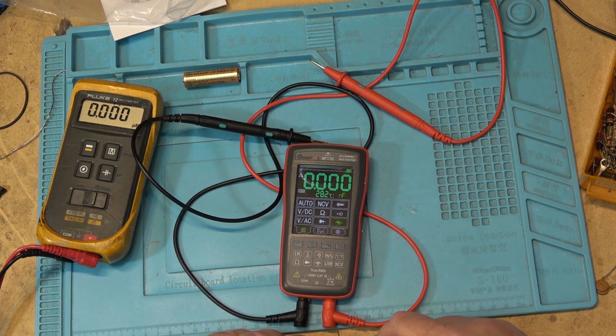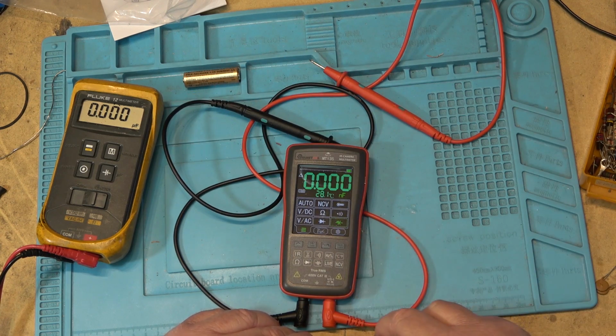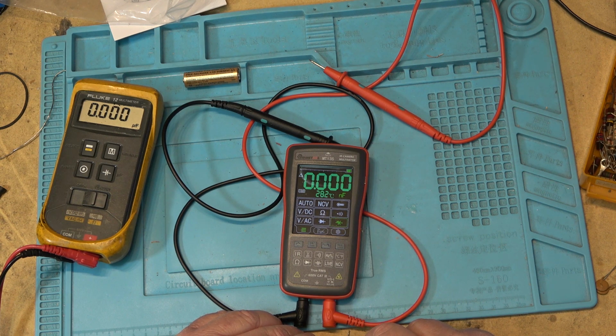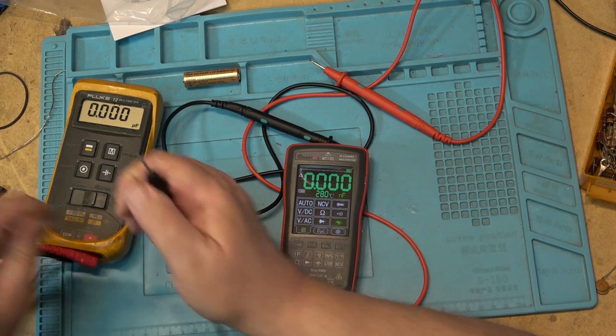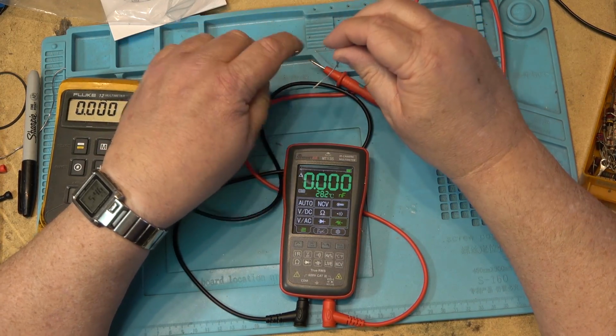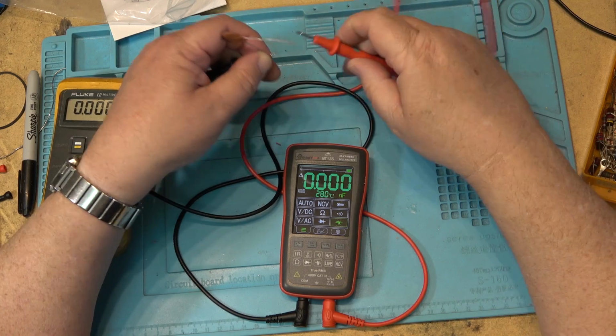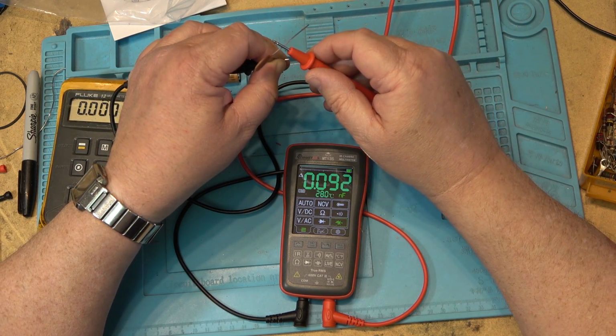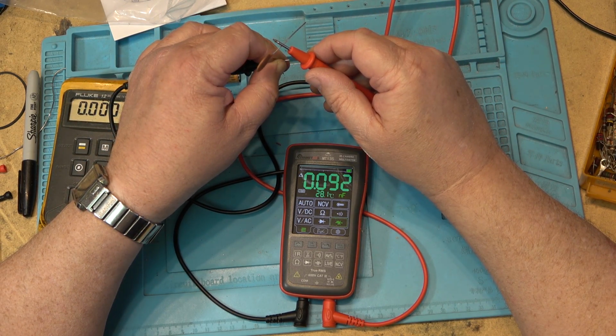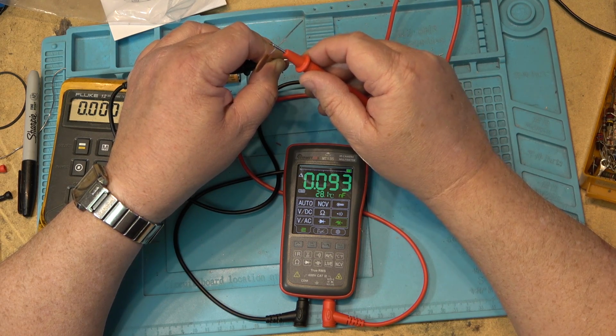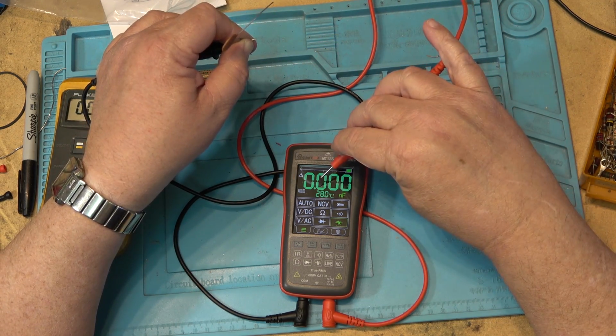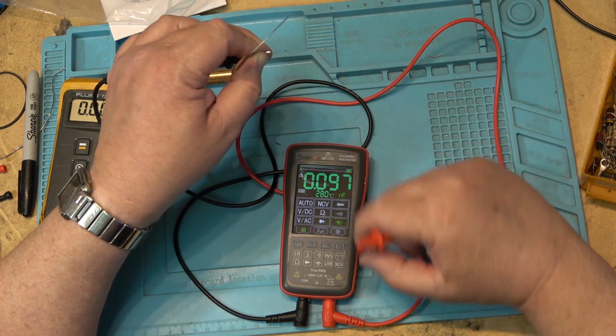It should. I don't want to touch it because I don't want my skin resistance to affect it. The Fluke might not measure that low because it's in microfarad mode. So interesting, the Fluke's not going to measure this cap. It says it's 0.00, but this one certainly is measuring 100 picofarads. 0.093, right? 100 picofarads would be 0.1 in measuring in nanofarads.